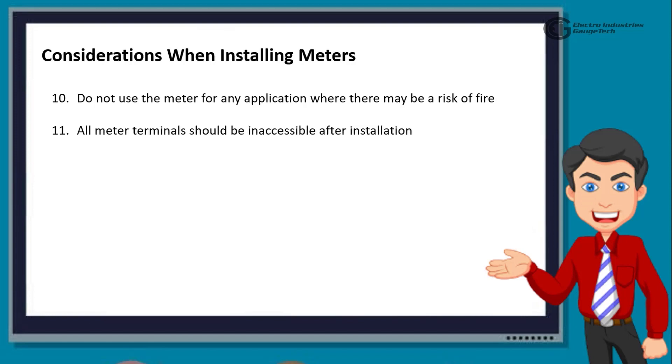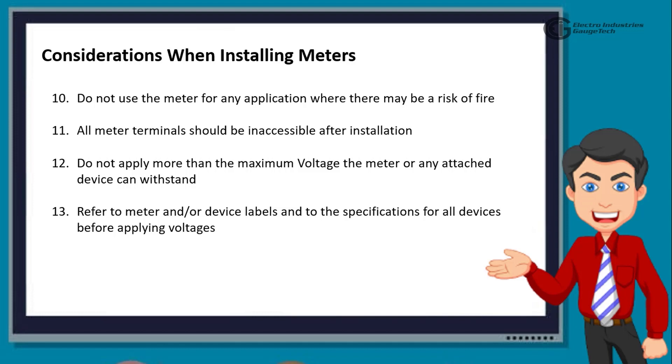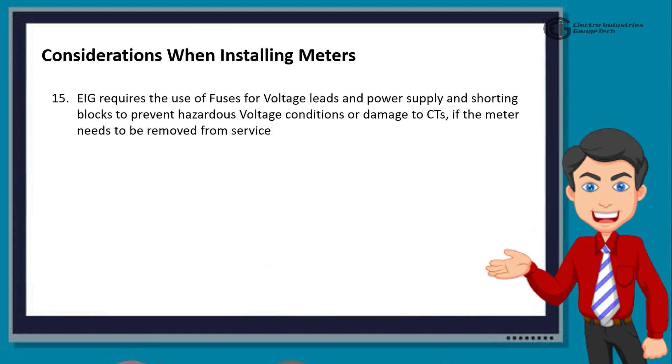All meter terminals should be inaccessible after installation. Do not apply more than the maximum voltage the meter or any attached device can withstand. Refer to meter and/or device labels and to the specifications for all devices before applying voltages. Do not HIPOT dielectric test any outputs, inputs, or communications terminals. EIG requires the use of fuses for voltage leads and power supply and shorting blocks to prevent hazardous voltage conditions or damage to CTs if the meter needs to be removed from service.